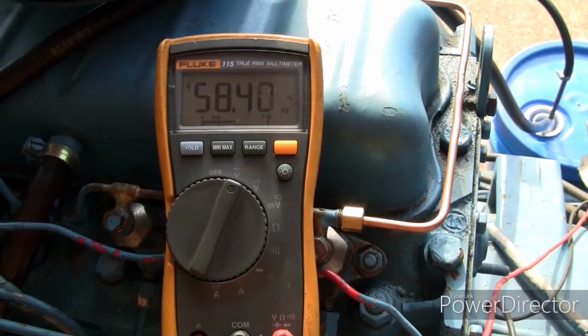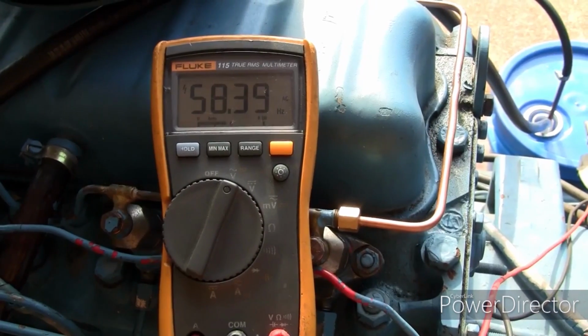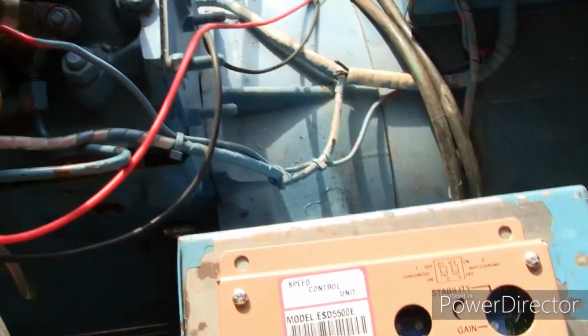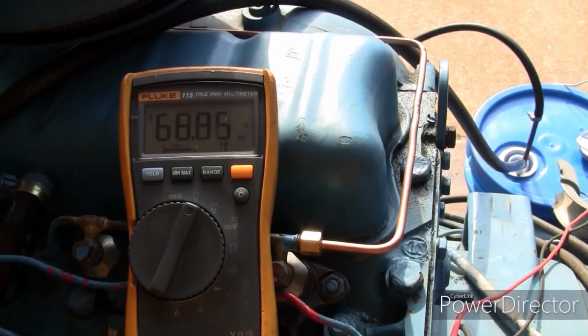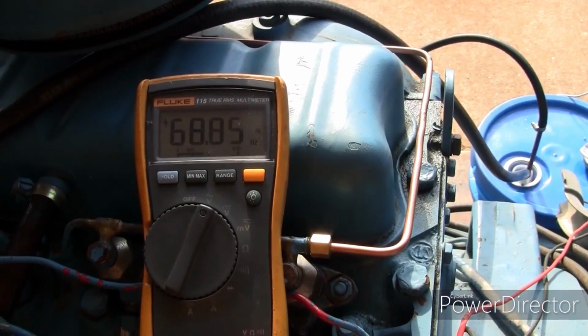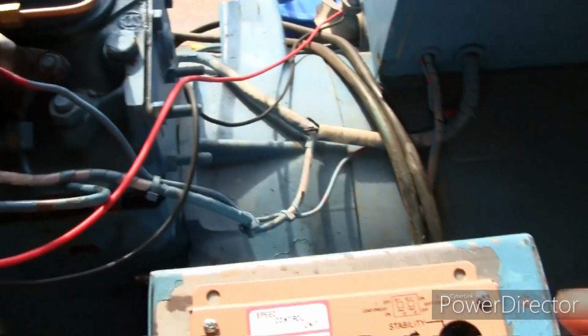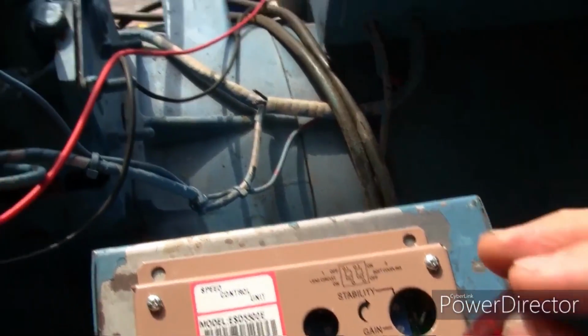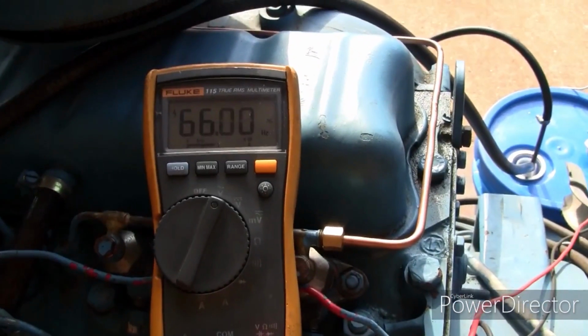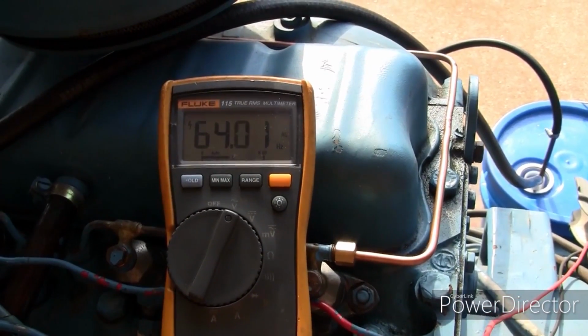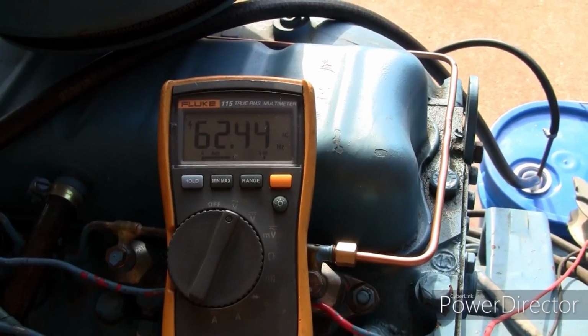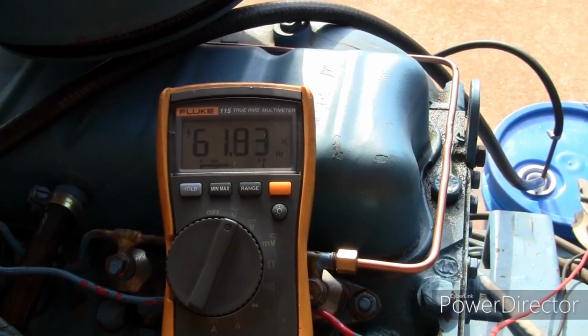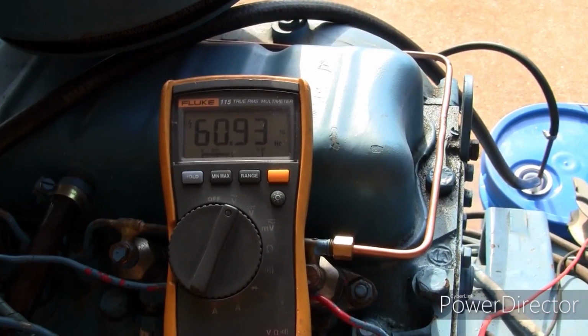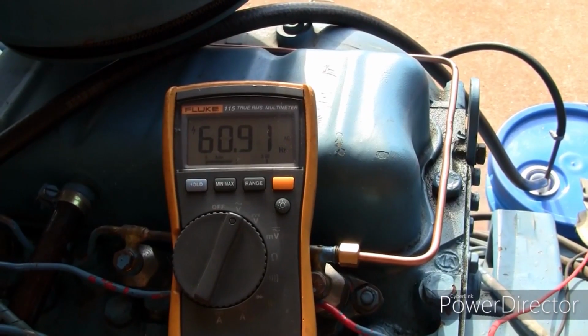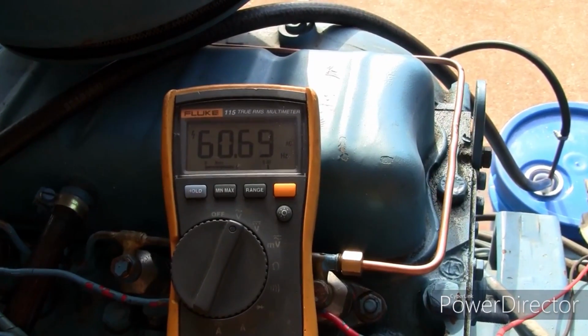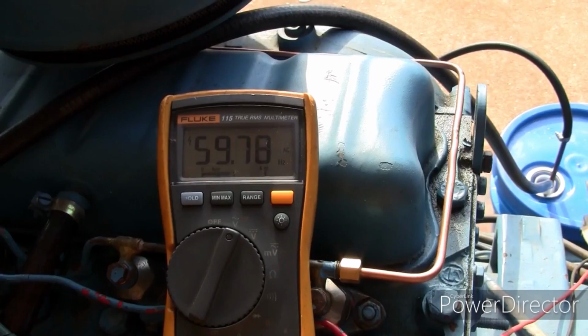So you'll note that the speed is going to overshoot. We're just sitting here at 58 hertz, we haven't hit the threshold. Oh, here we are, so we're at 68 now. So now I'm turning it down counterclockwise. Now the reason it shot up so rapidly is a result of the fact that I have the gain and the stability turned way down, so that the governor is responding very, very sluggishly to my set point adjustments.